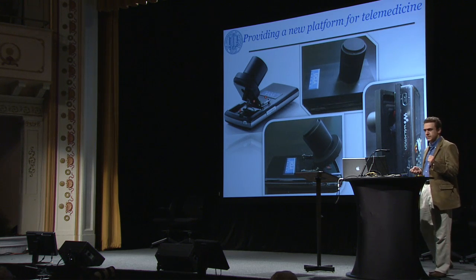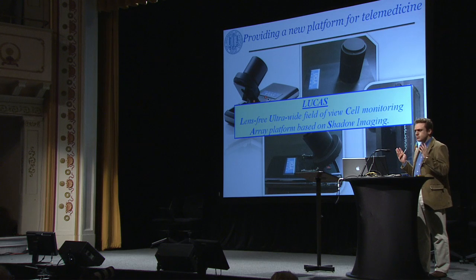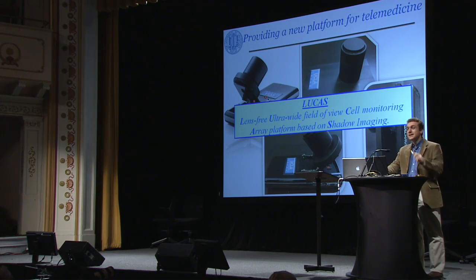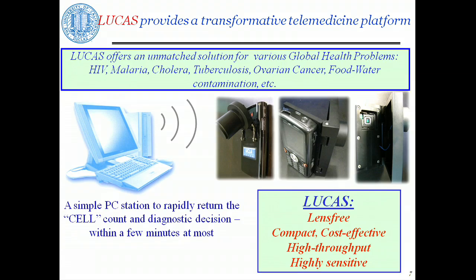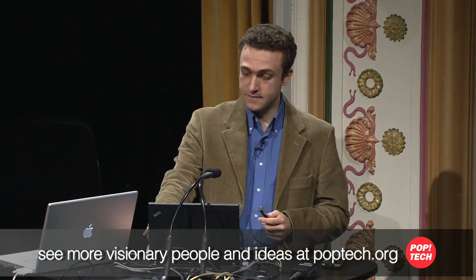What you're seeing here are some prototypes from my group. The underlying technology is called LUCAS — it stands for Lens-Free Ultra Wide Field of View Cell Monitoring Array Platform Based on Shadow Imaging. The shadow imaging part is the really important part, because instead of imaging the cell with a lens, we image its shadow. As you would know, the most expensive part of a camera or microscope is the lens. We get rid of that totally, which saves us money and weight, making it extremely compact, cost-effective, and at the same time very sensitive.